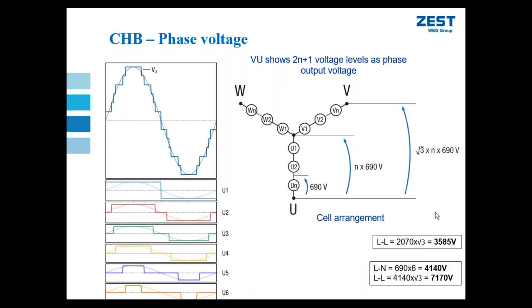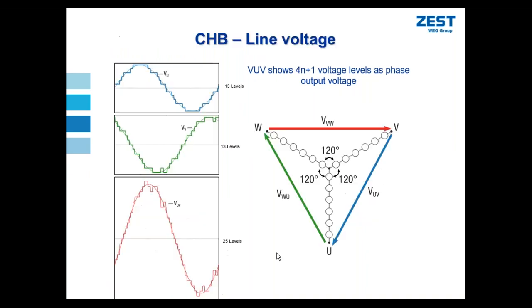If I look at a 6.6 kV case, I now have 6 690 volt power cells per phase, so my line to neutral voltage can be extended to 4140 volts. For my line to line voltage, I multiply that by the square root of 3, and that takes me up to 7170 volts. So that is why a 6 power cell per phase drive is used for 6.6 kV applications.